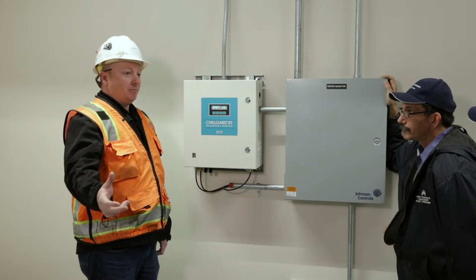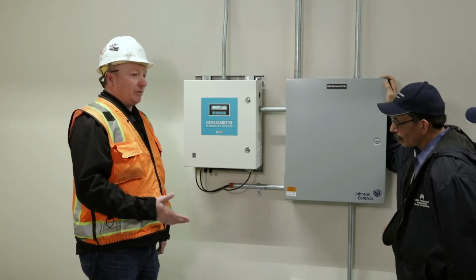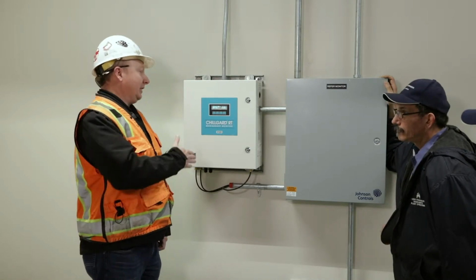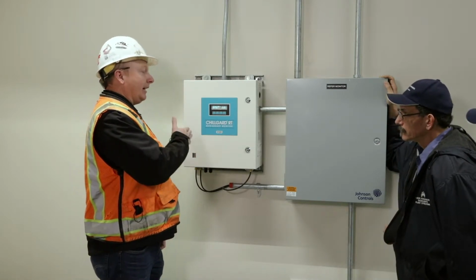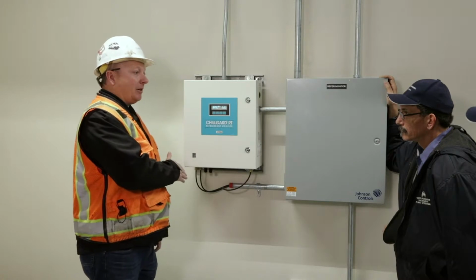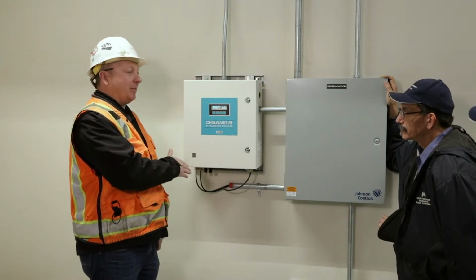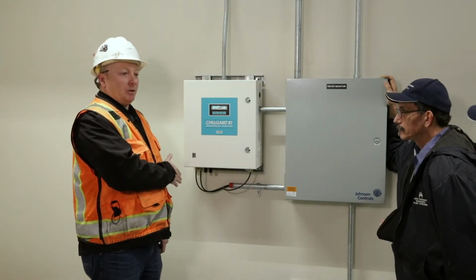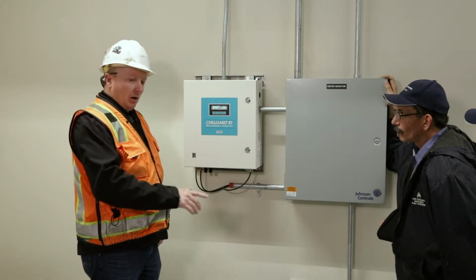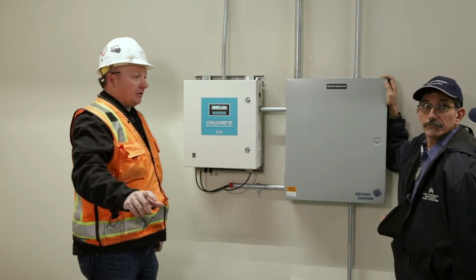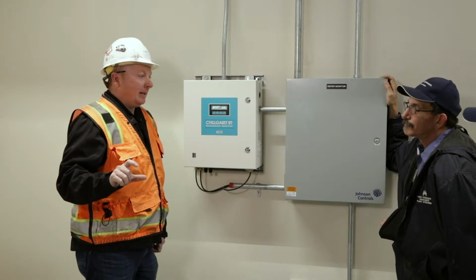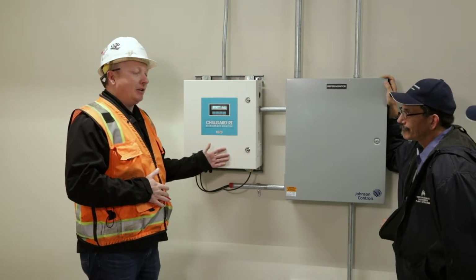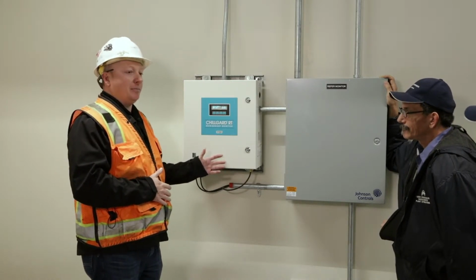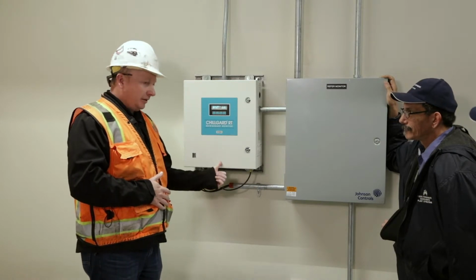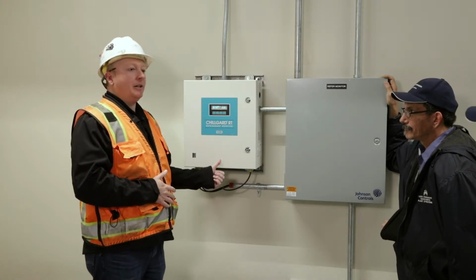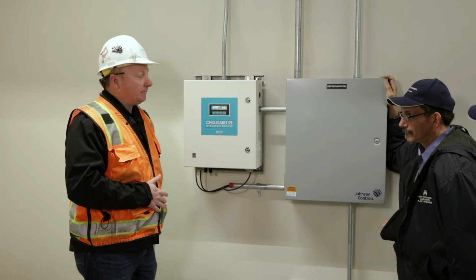It's constantly drawing air in, sampling for refrigerant. If we detect anything over, I think 70 parts per million out here, or no, I'm sorry, 700 parts per million, that's when we're gonna go into a shutdown alarm. On those probes that are under the chillers, they have filters on them. The manual's in here. I don't remember the frequency that they're supposed to be changed, but we have spare filters in the panel here with all the instructions on it.